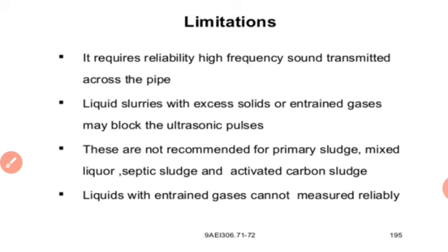Now limitations. It requires reliable high frequency sound transmitted across the pipe. Liquid slurries with excess solids or entrained gases may block the ultrasonic pulses.